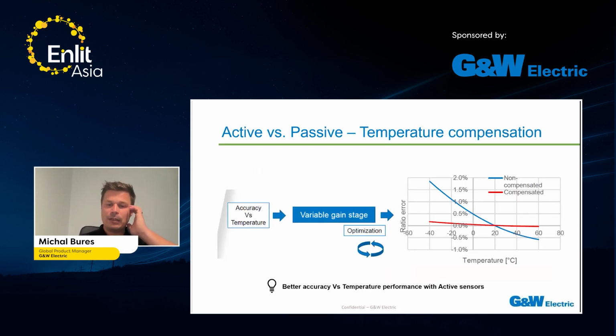The other thing which is different when we are comparing active and passive sensors is temperature compensation. The critical point is to keep the accuracy at the same level, no matter what the environmental temperature is. In the chart, you can see the difference between active and passive sensor, where we see linearity over the whole range for the active sensor, thanks to the electronics inside. And the blue one is the non-compensated, passive one. So you can see that the accuracy and the ratio error can be different at different temperatures.